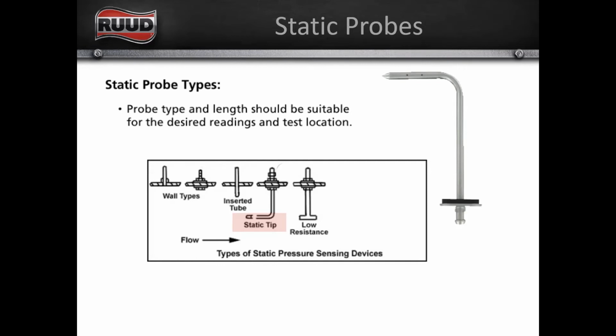And we want the bend, or we want this, to be facing directly into the airflow, with the two holes pointing against the sidewall of the duct. That ensures that the same static that's being pushed against the sidewall of the duct is also being pushed against the side of the static pressure probe. And you can see down here where it shows the airflow, we've got a little pink square around the static pressure tip. That gap, or that void, in this static pressure probe is supposed to represent the holes.